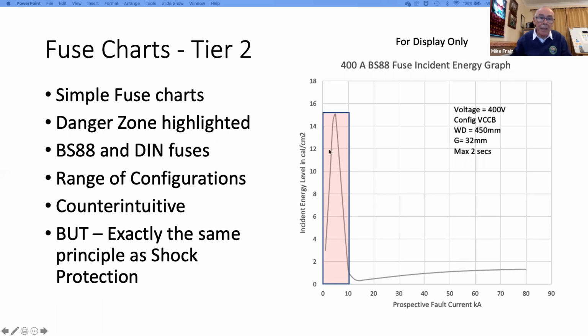what we've got is a plot of incident energy level against fault current along the bottom. And 80,000 amps, by the way, is the maximum withstand capacity of a BS88 fuse. But as you can see, the vast majority of the curve is above 10,000 amps. So what you do know is that if it's below 10,000 amps, that is where we've got a danger zone. That's where we've got to start thinking a little bit more carefully about what the incident energy level is actually going to be at that point. But it gives a quick and easy yes or no to whether we're in the danger zone or not. So there's a range of configurations.